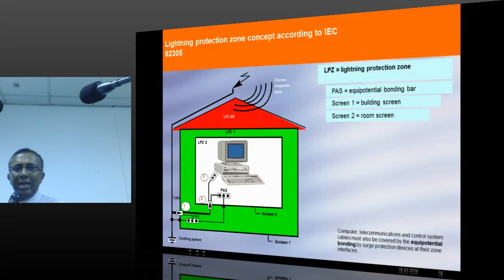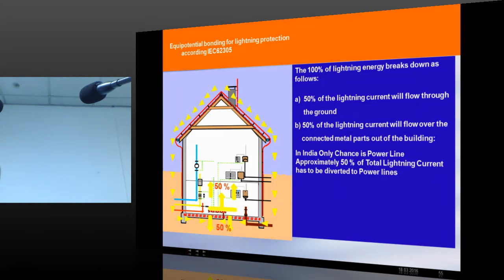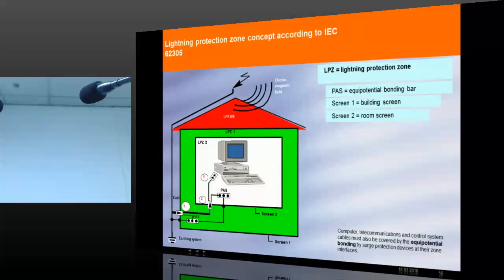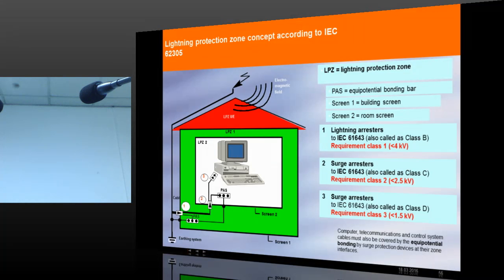So this is, I skipped that particular slide because current flow 50% goes to ground and 50% gets coupled into the building, and what we need to do is this 50% which is coming inside needs to be diverted through the services. So, the other condition I told you, in order to call this area lightning protection zone 1, that means the green area, one of the conditions is requirement class 1, less than 4 kV. The maximum amount of transient voltage allowed in this place is 4 kV.